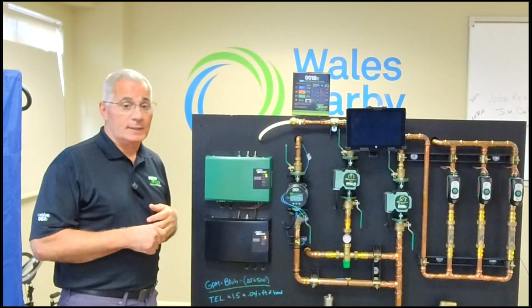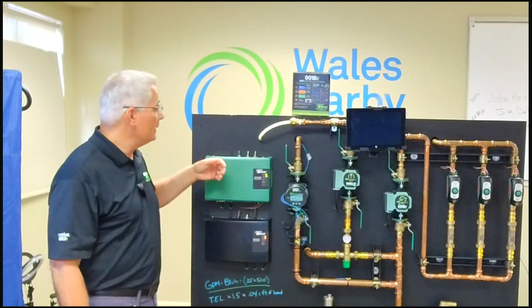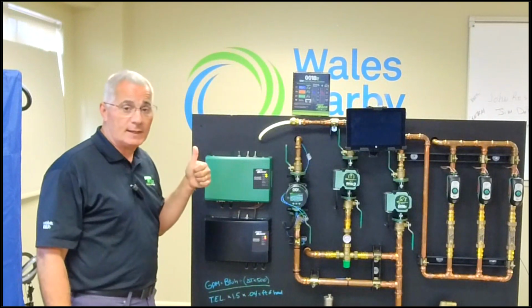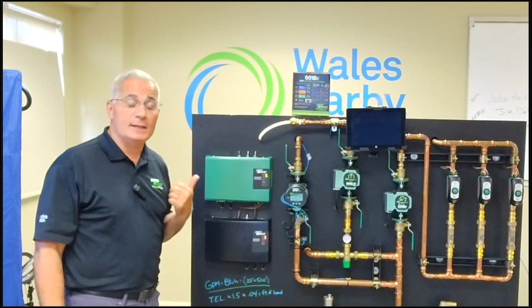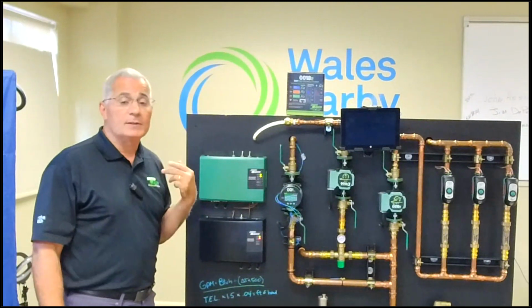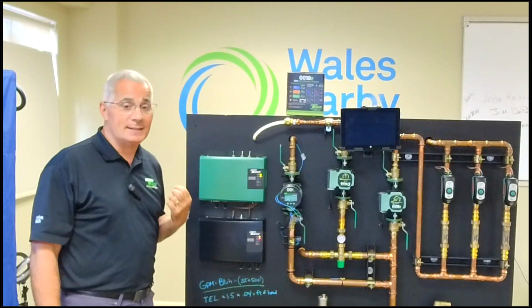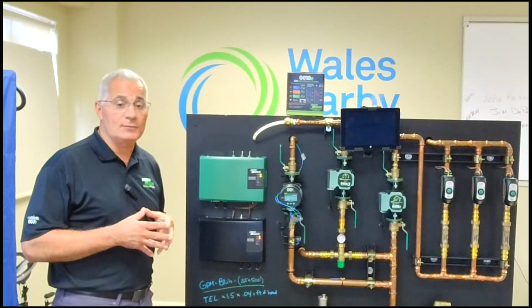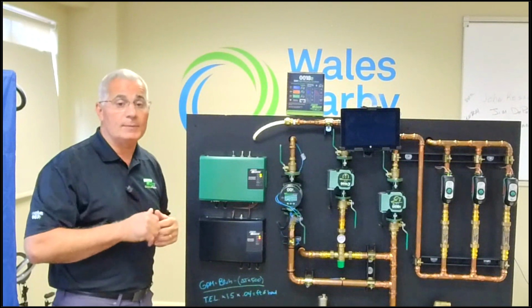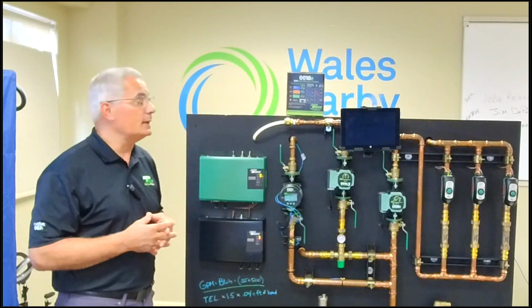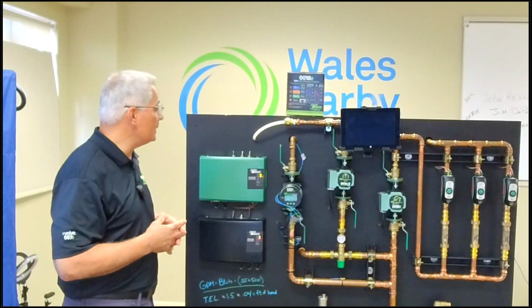So again, as a troubleshooting tool, if I saw the green light, yes, I've got power. I see a yellow light, yes, I have a call for heat. But if I don't see a red light, that is telling me my problem is at my zone valve. I haven't opened it up and made the end switch, and that's going to direct me to what I have to do to get the system up and running.